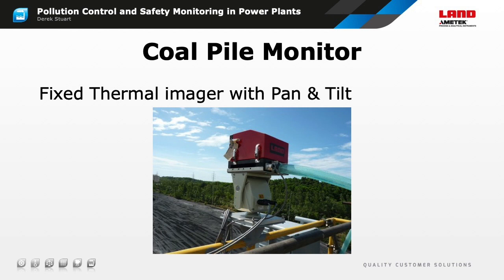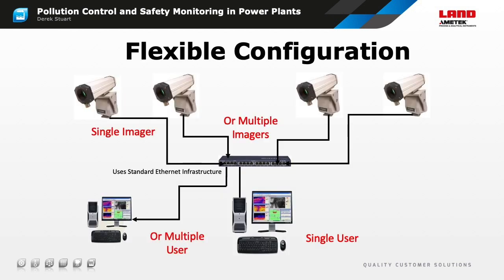The illustration shows a fixed thermal imager with a long focal length lens attached to a pan and tilt mount. This arrangement allows it to repeatedly scan across the storage pile to give a high-resolution image without sacrificing coverage. Depending on the size and geometry of the storage area, several separate thermal imagers may be needed. The system illustrated here has 4 imagers with 2 remote consoles displaying the images and processing and storing the data.